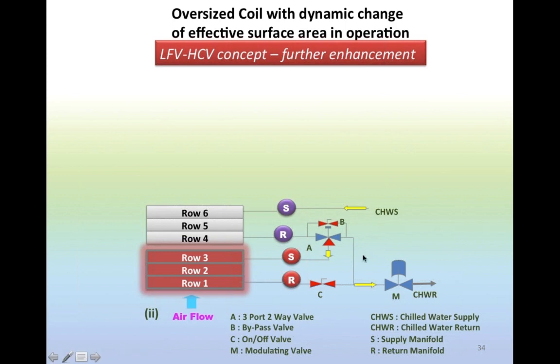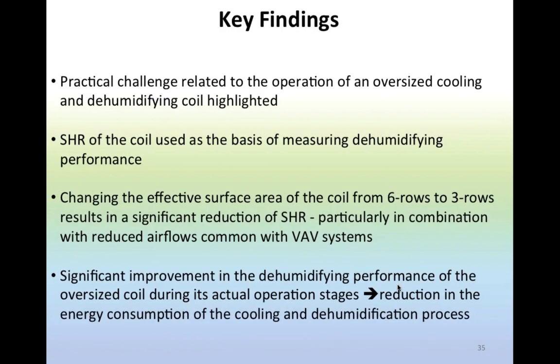When you have a smaller cooling coil, the modulating valve that was closing in the earlier 6-row configuration, I can open it up and bring it back to my design flow rate. Remember the high coolant velocity I mentioned as a part of a requirement? I combine the low face velocity together with the high coolant velocity at part load, and I get the best dehumidifying performance. So the key finding from this particular study was that the practical challenge of an oversized coil can be mitigated by working with an effective surface area reduction through the operation stage of the coil.